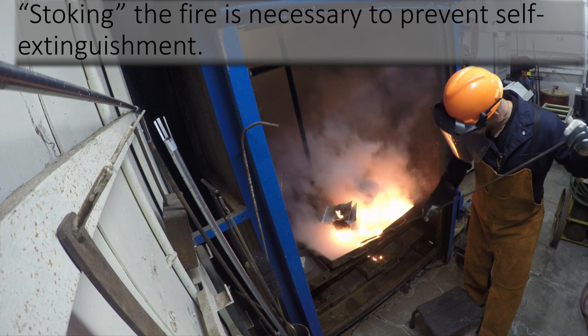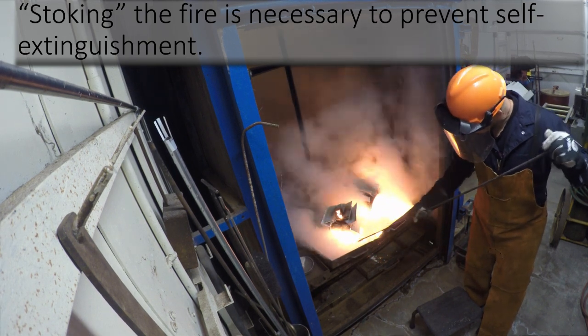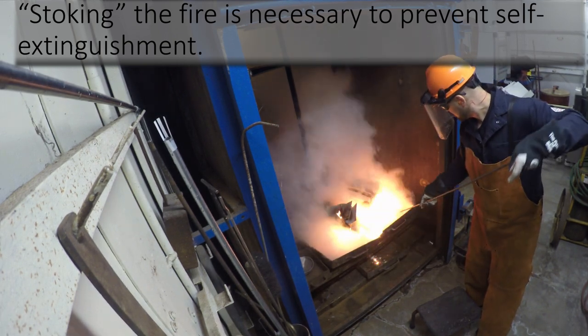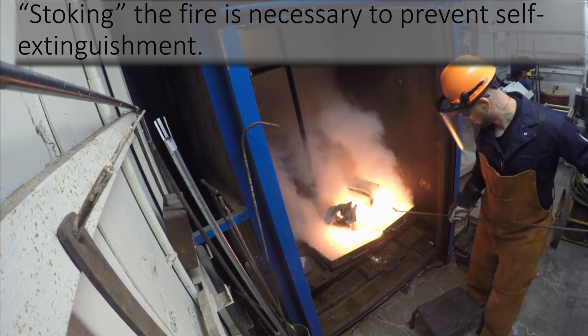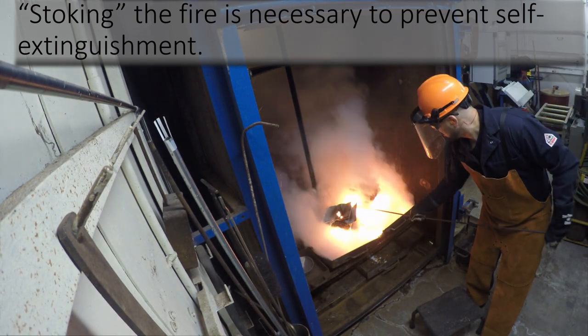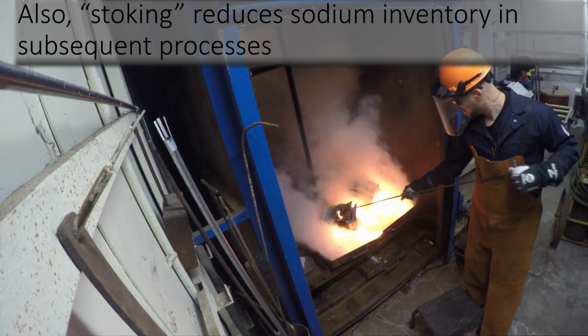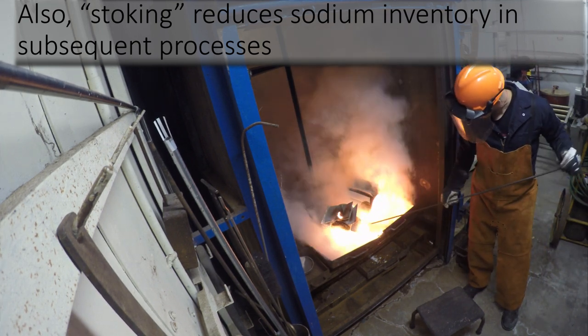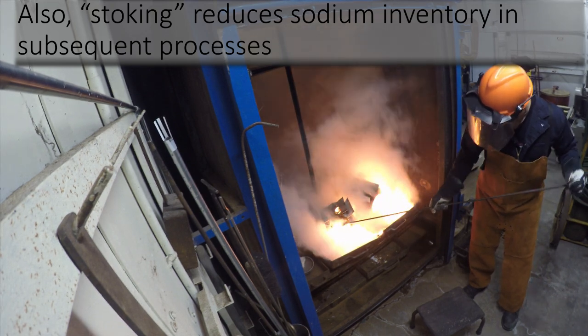When the fire becomes self-sustaining, an operator must monitor the fire and stoke it with a metal prod to ensure that the fire does not extinguish itself. Sustaining the fire by stoking ensures that the fire goes through a complete burn, which reduces sodium inventory in subsequent processes.